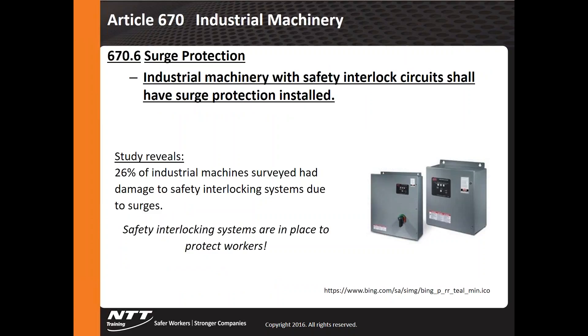Article 670.6 covers surge protection for industrial machinery. If industrial machinery has safety interlocks, it shall have surge protection. Research found that surges had damaged safety interlock systems, raising questions about whether they were still functioning correctly. The code now requires surge protection to help protect workers from failures in machinery safety interlock systems.